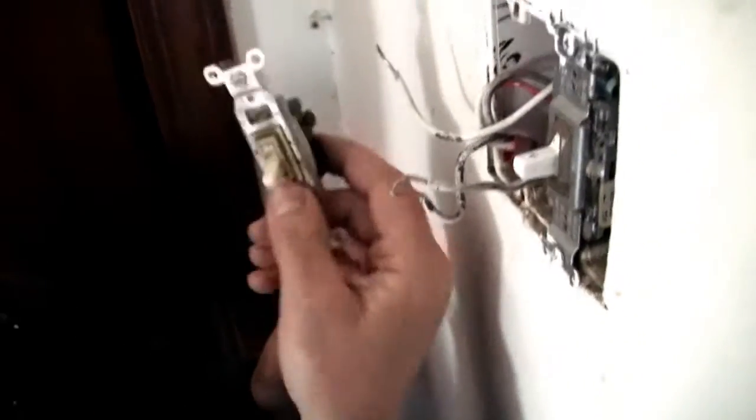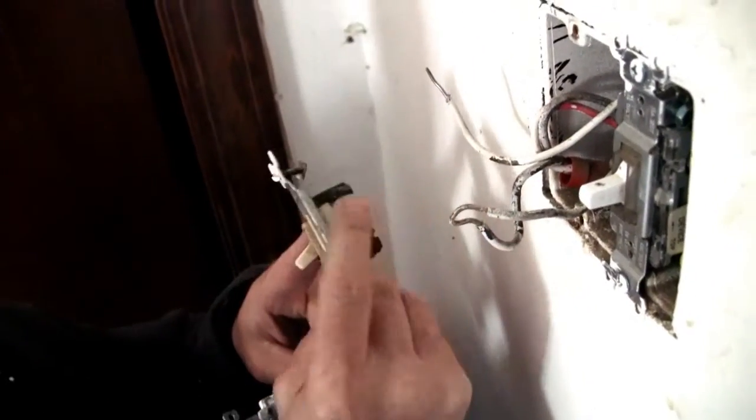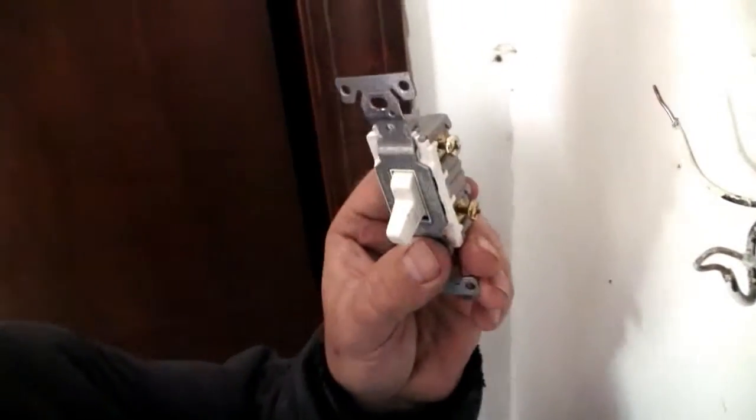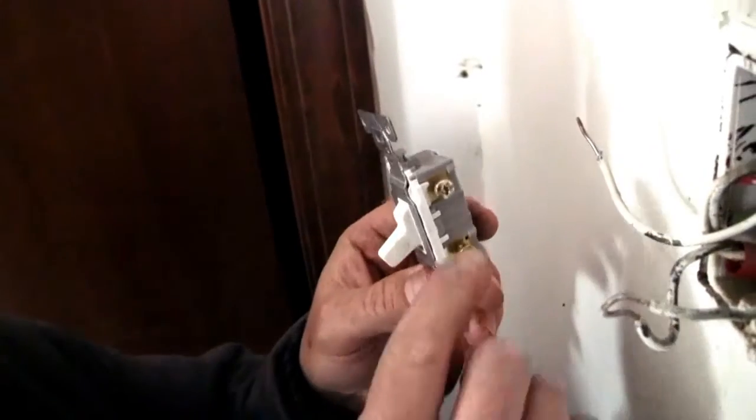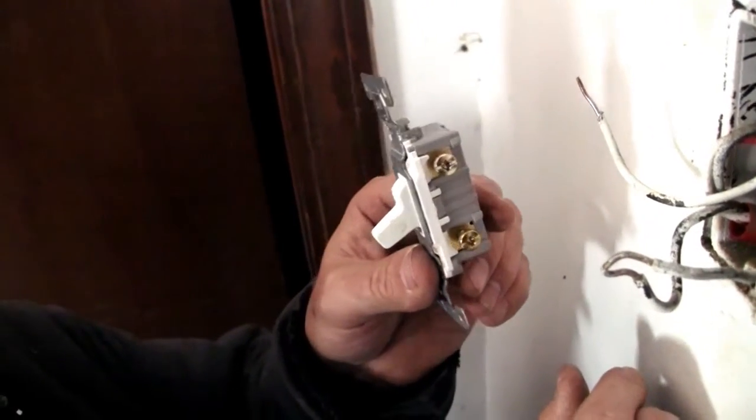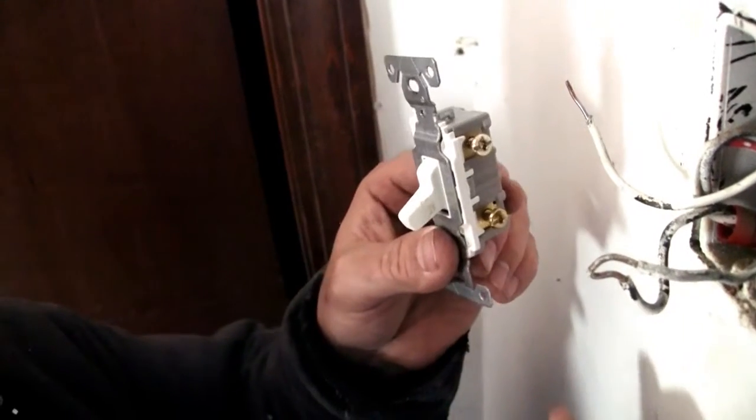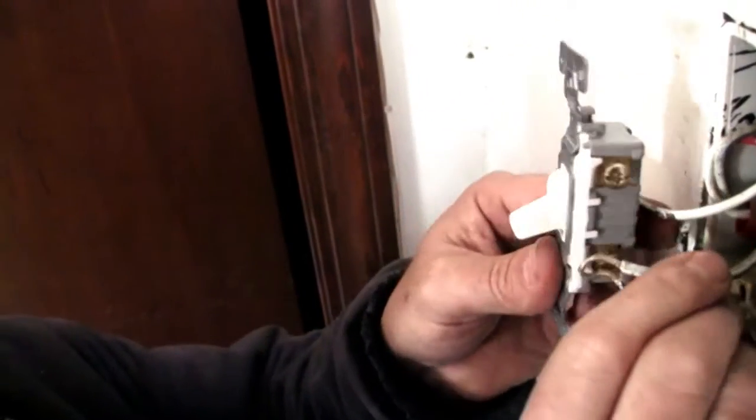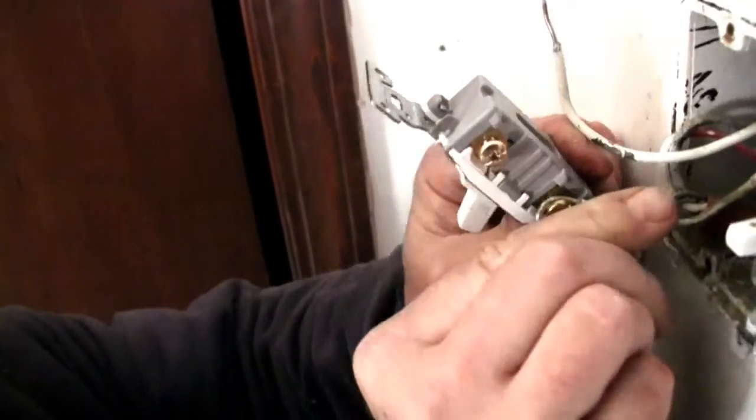This is the old switch and it had the screws on each side of it. This is the new switch. Even though it's not exactly like the old one, it works the same way. There's one at the top and one at the bottom and it really won't matter which one goes on the top and which goes on the bottom because they're both hot wires. The hot wire which is the black wire attaches to the brass screws.